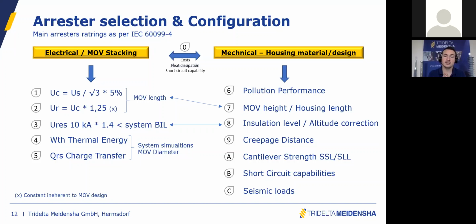Then comes the energy ratings. A very important topic, because you want to make sure that your MOV blocks are dimensioned to withstand the stress coming from lightning or from switching. There are two important MOV energy ratings: the WTH, the thermal energy, and the QRS, the charge transfer. I have two slides afterwards that will show more details about these two ratings. If you look at my screen, you will see that these two blocks have two different diameters, and the diameter of the blocks has to do with the energy rating. So the larger the block, the higher the energy rating. But the larger the block, the more difficult it is to manufacture. So here comes the challenge.